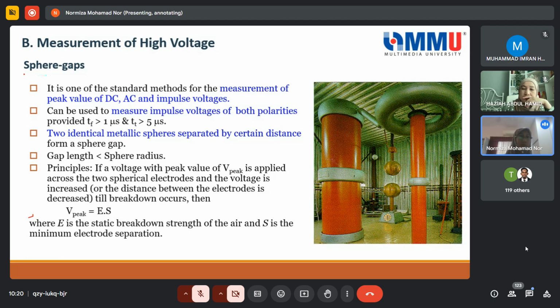But anyway, first we try to understand what is the sphere gap. The sphere gap is used to measure for the DC. It can be used for all voltage types, DC, AC, and impulse, and it can be used for both polarities. But you will see later on the disadvantage of the sphere gap is that it's very much affected by the polarity. For example, if I want to measure at 30 kV positive, maybe at 30 kV it causes breakdown. But if I were to measure under negative, I have to use higher voltage. So the reading will give you different readings.